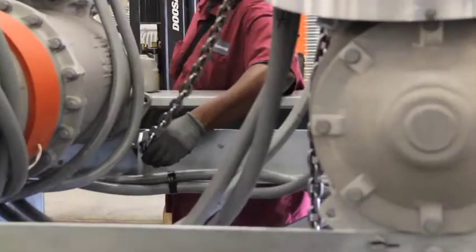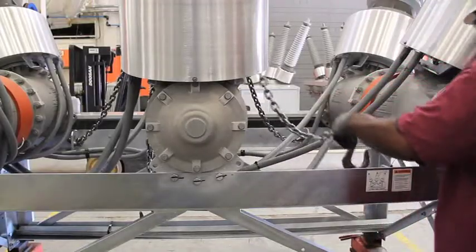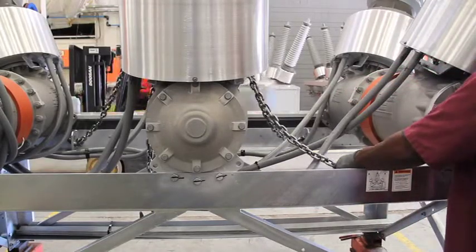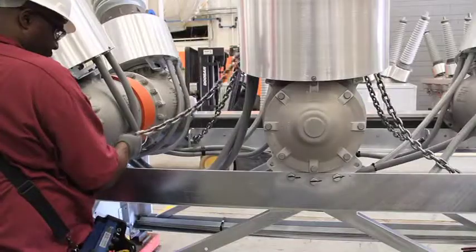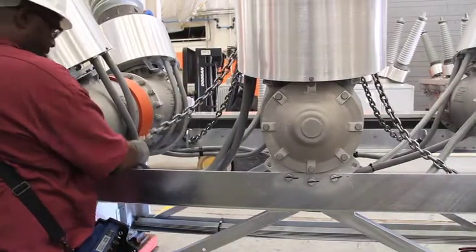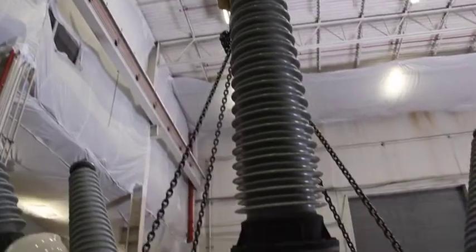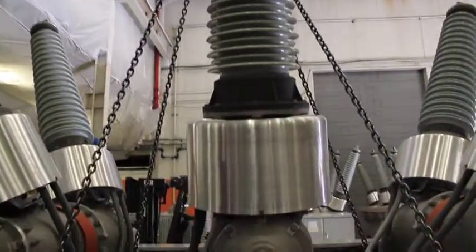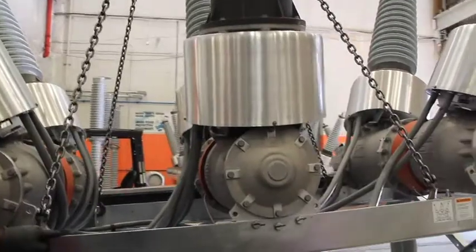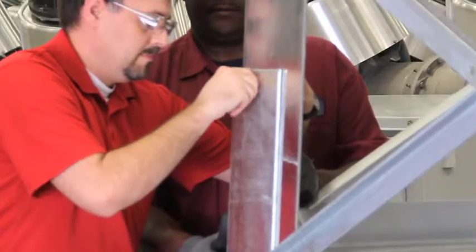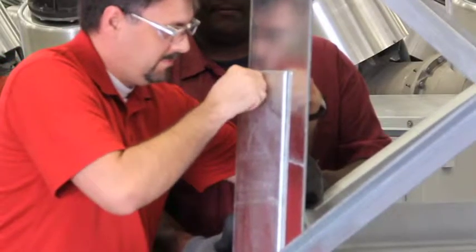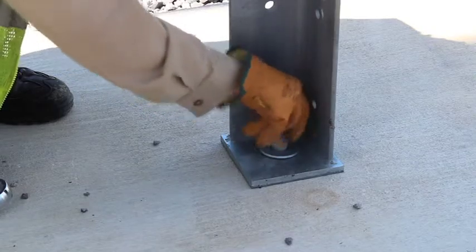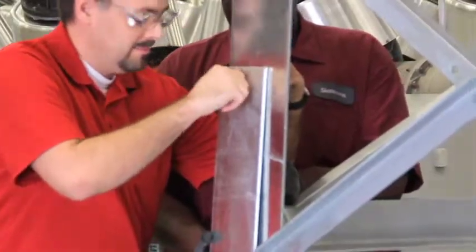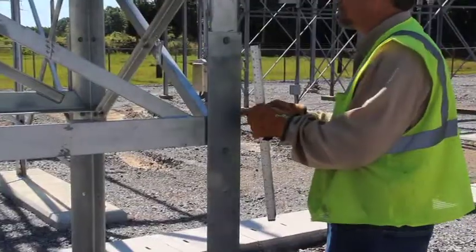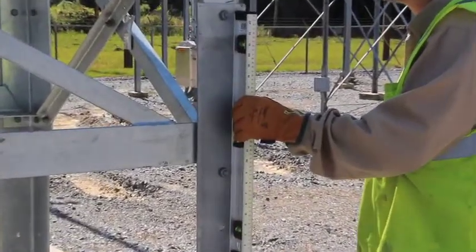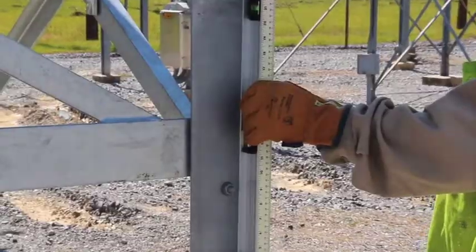On 72 kilovolt and smaller breakers, lifting is accomplished by attaching 3 9-foot hook chains to the 3 lifting lugs mounted on pole units A and C. The 121 kilovolt and larger breakers require 4 9-foot hook chains attached to lifting lugs on the frame. The legs should be first assembled to the breaker, then the breaker assembly bolted to the foundation. Bolts should be firm but not tight to allow proper alignment. Insert shims if necessary under the legs to level the breaker before tightening the foundation bolts.